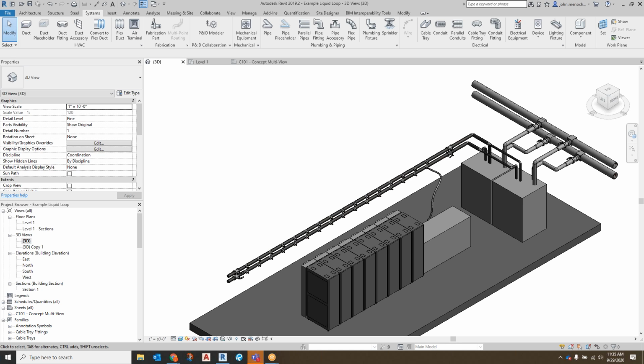The other piece I'd throw out is that in existing data centers converting from traditional air-cooled solutions to higher density stuff, a lot of times they're pulling out CRAHs and wanting to connect back into the connections where the CRAHs were sitting before. Whether that be a CDU, or like Don was talking about, do you put in taps for drops for 15 racks off the main? No, you wouldn't come off of where the connections for that CRAH were, you'd run a new header that has the taps off of that, kind of like what John Minash is showing here, maybe with or without the CDU in the middle.